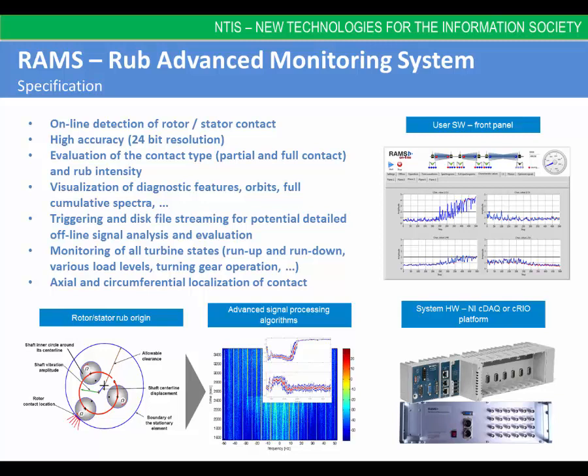The RAMS software was written in LabVIEW and offers understandable visualization of diagnostic features: orbits, full cumulative spectra, phasors, and much more. The software also allows defining triggers for signal streaming to a storage medium for potential detailed offline signal analysis and evaluation. The RAMS is able to monitor all turbine operation states such as run-up, run-down, various load levels, or turning gear operation.